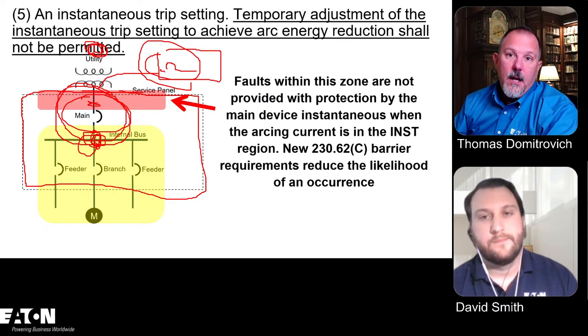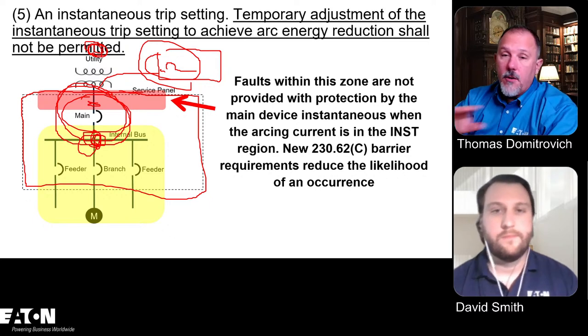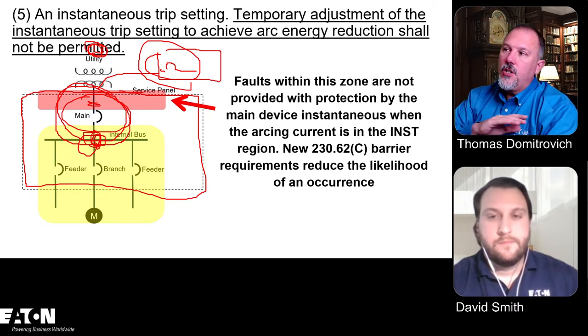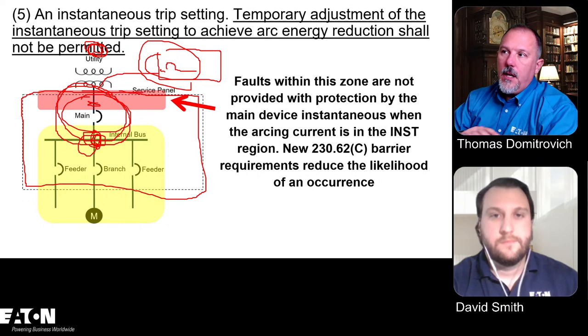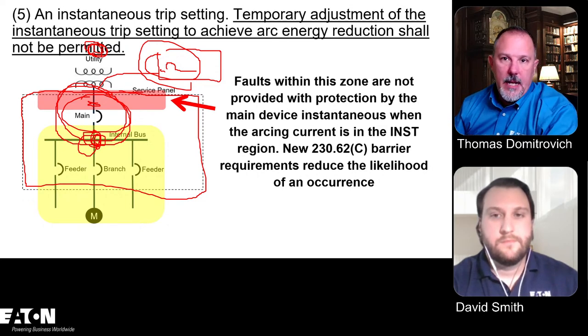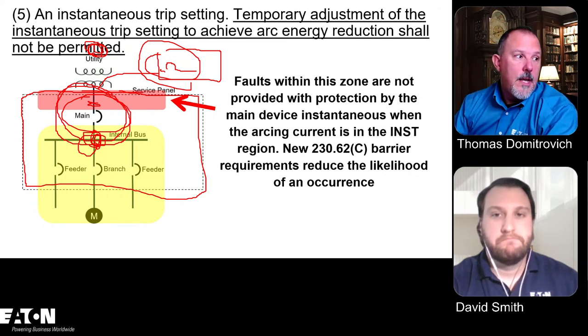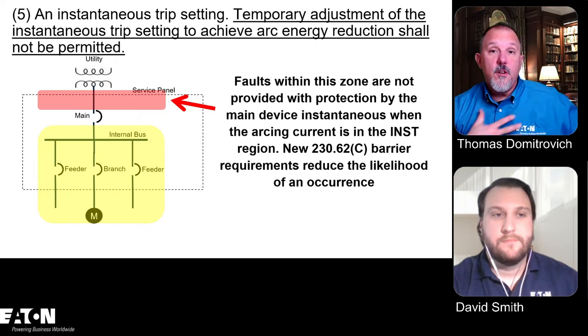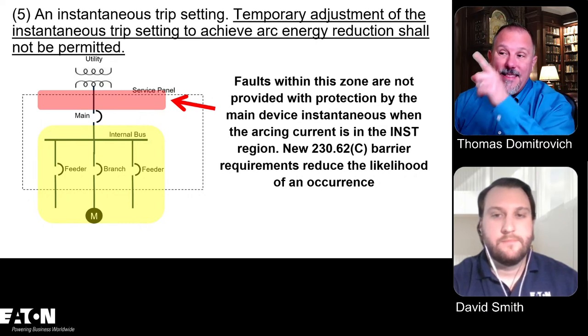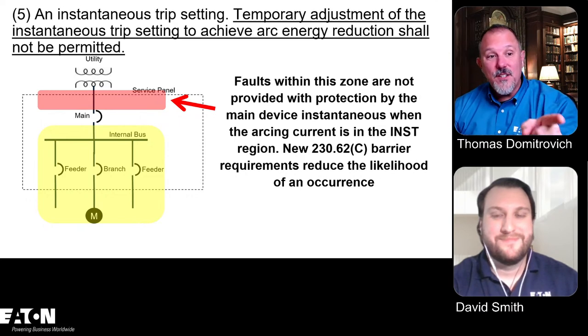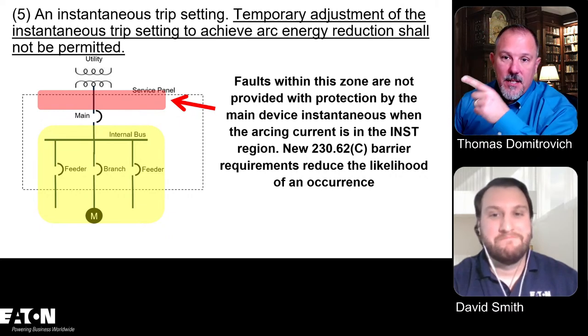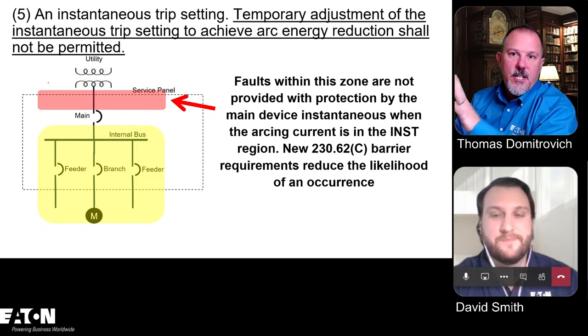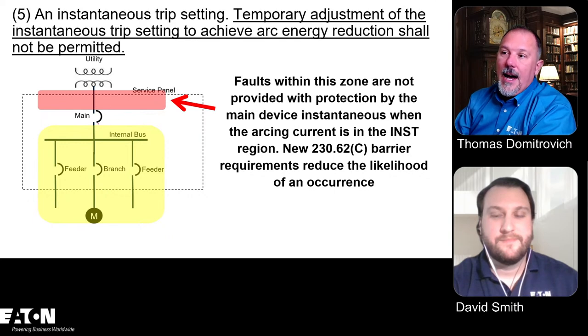And you know what? That goes for any of the technologies listed in 240.87, whether it be the arc reduction maintenance switch, instantaneous, zone selective interlocking, the arc quencher, the active arc flash mitigation system, differential relaying, any of that. It is the same issue with line-side propagation. So Mr. Ross has a very good observation, which is part of one of the issues that I have with 240.87. That's why these slides were created, because of what Ross pointed out. In this application that I'm showing you, the red zone, you don't have protection for a fault on that side. And if I have line-side propagation, I have...